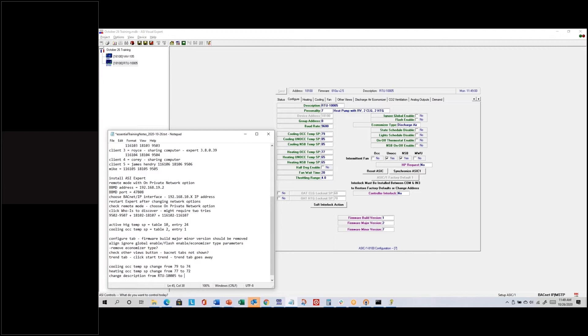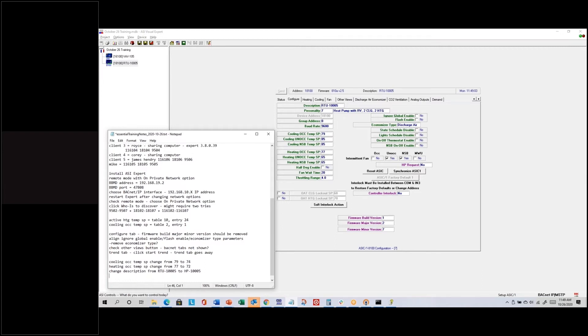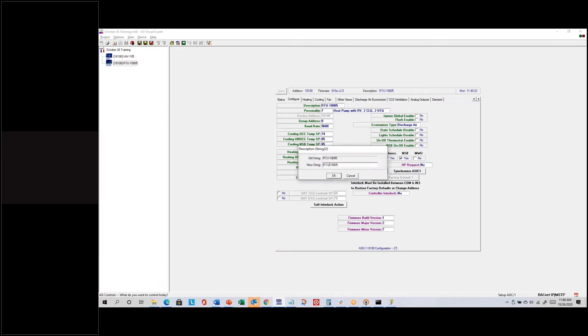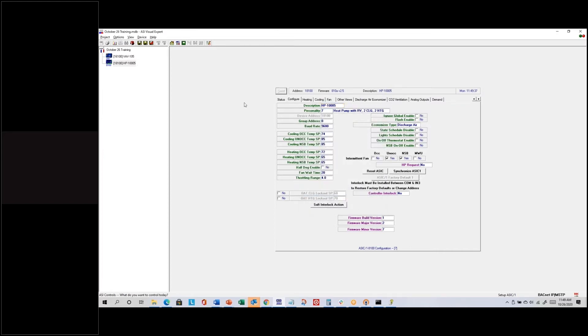So we'll see that the set points will go back and change according to the file I load in, but the description is not going to change — that's intentional. This demonstrates that loading changes most things but not everything. The background of the setting is marked in yellow, which means I can click Send to push it down into the controller. Now I'll go to the load disk icon.